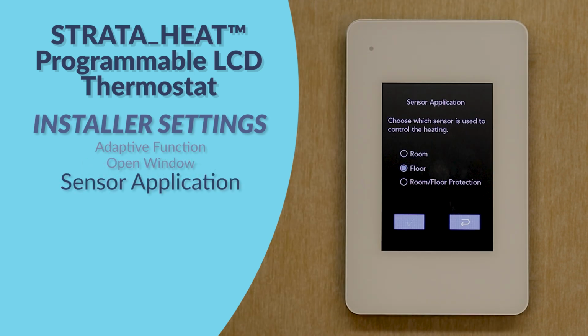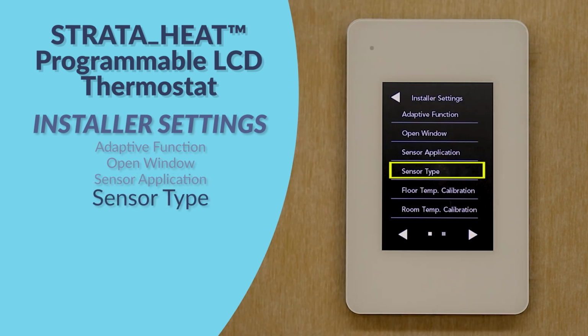The sensor application function is used to choose which sensor will control the heating. The room setting uses the built-in air sensor, while the floor setting incorporates the floor probe to control heating. The room floor protection setting uses the air sensor, but is limited by a maximum set floor sensor setting. The maximum floor temperature setting is set in the floor protection installer setting. Sensor type. In the event that you're not using the supplied sensor, this thermostat offers the ability to choose another sensor type.